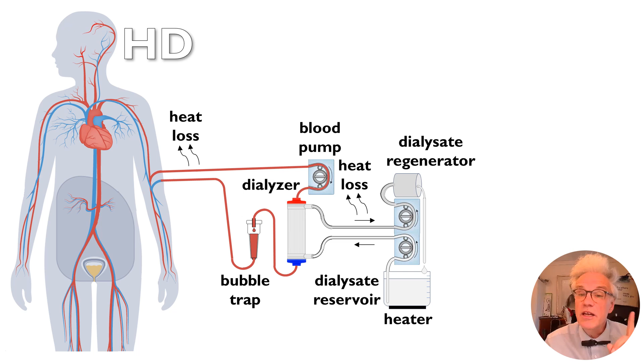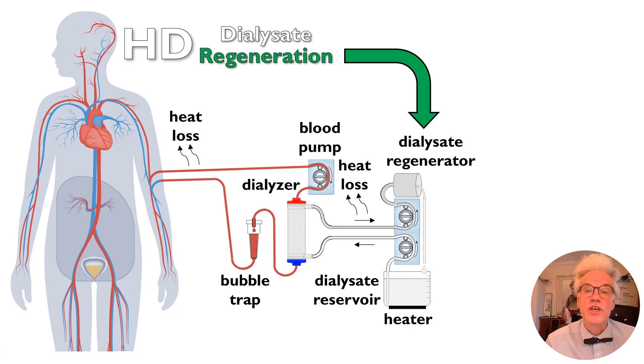But a lot of water, and thus electricity, might be saved if we reuse the dialysate. And as you see here, the dialysate goes through the filter many times. You need a much smaller volume. A device that only uses 5 liters of dialysate is being CE marked at this very moment. You also lose much less heat because it stays warm. It only has to have a little bit of extra heat when it comes back to the patient. That is good news. You're saving water and saving electricity with such a principle, and you can make it smaller. And so this dialysate regeneration opens possibilities for miniaturization.